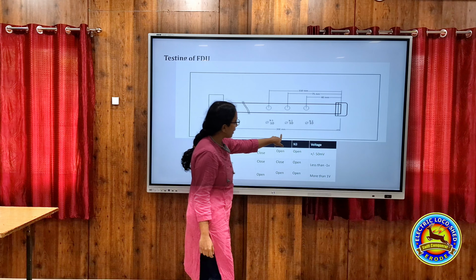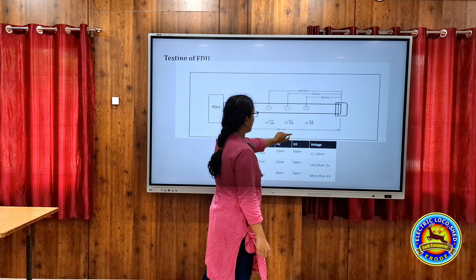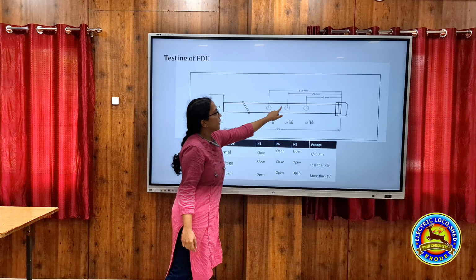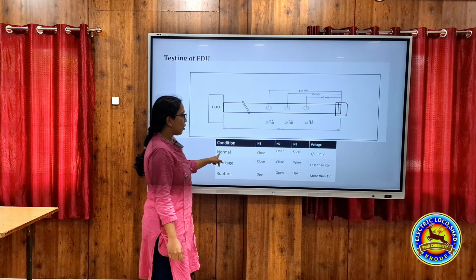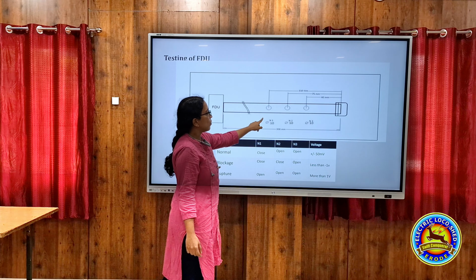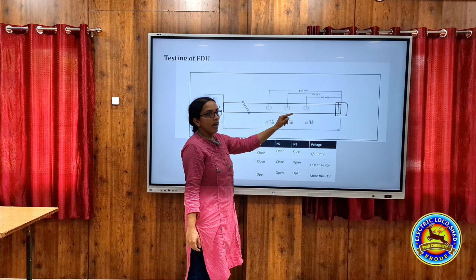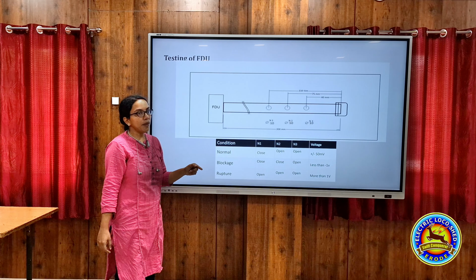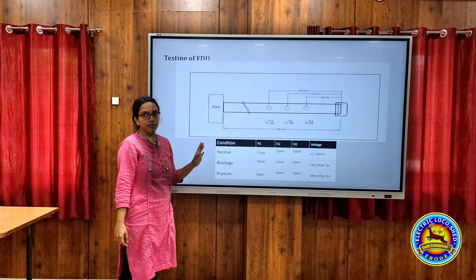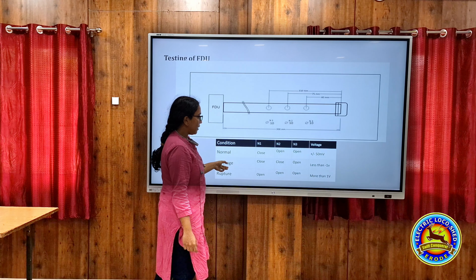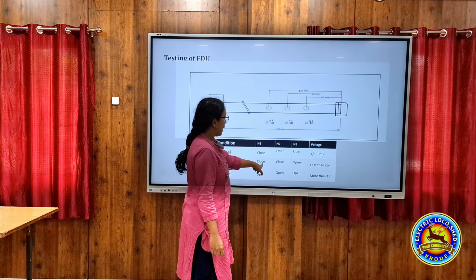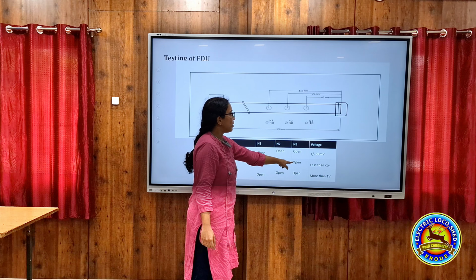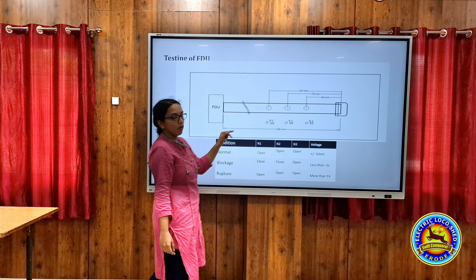This is the testing of FDU. For this, the FDU is connected to a 300 mm pipeline, and there are three openings, N1, N2 and N3. For a normal condition, N1 is in closed condition, N2 and N3 are open. Then the voltage is measured. It should be plus or minus 50 or plus or minus 100. And for a blockage test, we will close N1 and N2, and N3 will be in open condition. Then we measure the voltage.